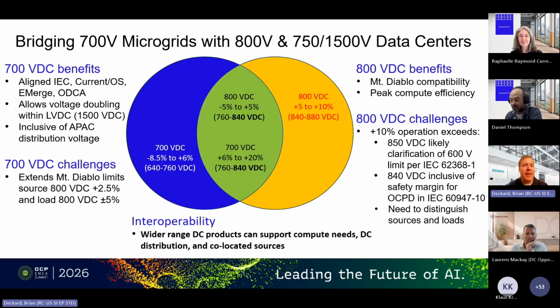This green area represents the common connection point, or hardware anchor, that we consider at 840 volts, which is plus 5% of 800 as well as plus 20% of 700. Why does that matter? Because standards such as the IT equipment standards already reference defaults of 20% for DC power, so the creepages and clearances you'd design for at 700 volts can also accommodate 800 volts with a narrow high-voltage tolerance.